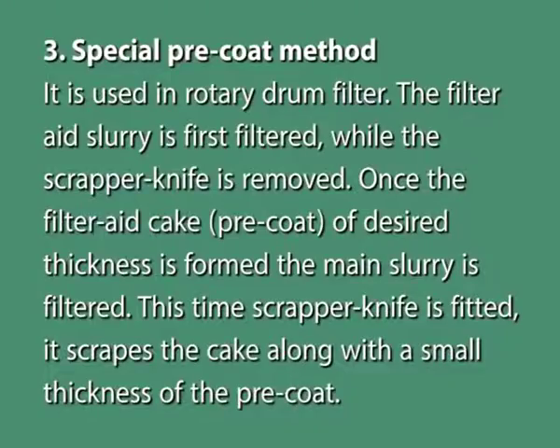The third is the special pre-coat method, used in rotatory drum filters. The filter aid slurry is first filtered while the scraper knife is removed. Once the filter aid cake known as the pre-coat of the desired thickness is formed, the main slurry is filtered with the scraper knife fitted. It scrapes the cake along with a small thickness of the pre-coat.